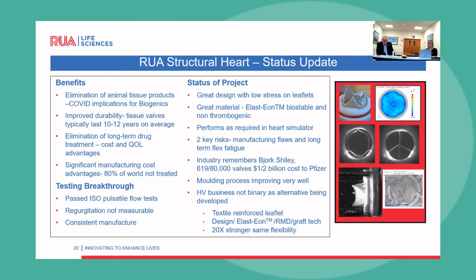Our status and where we are, we have got a fabulous design. The design that we've created has got exceptionally low levels of stresses on the leaflets, and that's been because if we use the same design that we used in the pericardium valves, a polymer will fail. It doesn't matter whether it's Elast-Eon or anything else, it will fail because the ultimate tensile strength of the polymer is substantially less than the ultimate tensile strength of the pericardium material. So we've had to reduce the stresses to create the durability of the valve.